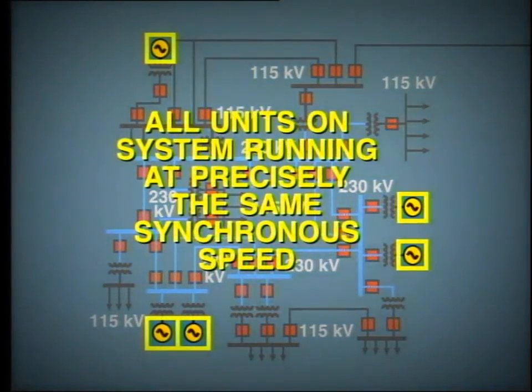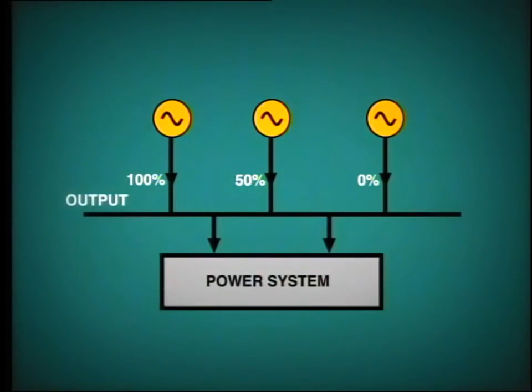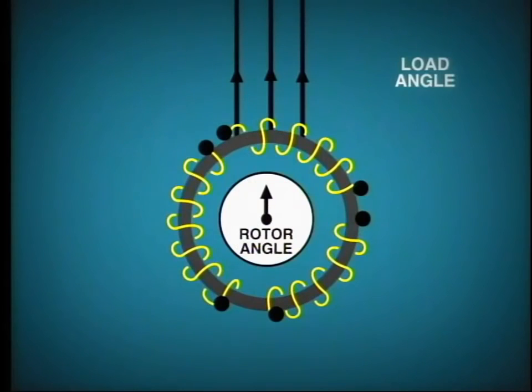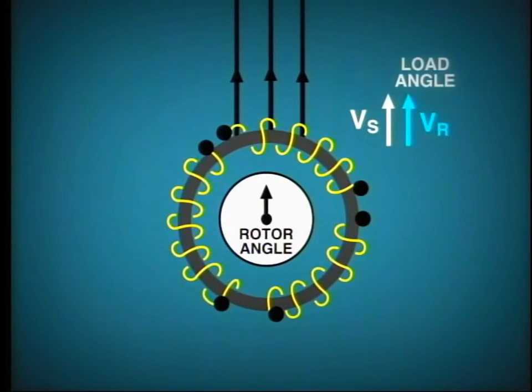Now remember, all of the units which are connected to the power system are running at precisely the same synchronous speed. This is obvious because they are synchronized together and the frequency is precisely the same at all points of the system. So how is it, then, that one unit may operate at, say, 100% capacity and another at 50%? Doesn't this mean that the unit with the greatest load is running faster? Well, beware of this trick question — of course it cannot run faster because the units are all synchronized together. So how does it put out more load? The answer is in the load angle or power angle. This is the relative angle between the induced voltage due to the rotor and the terminal voltage, which is dependent upon the power system. This diagrammatic representation shows the situation at zero load.